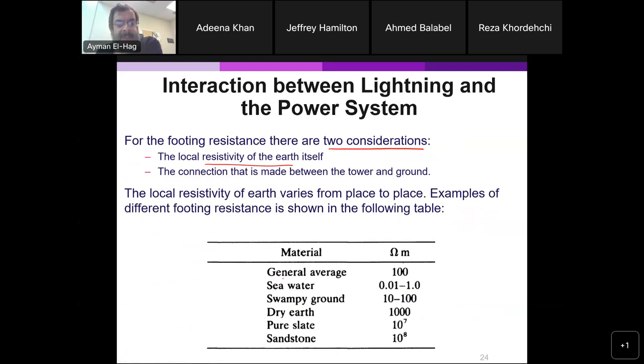So here it depends basically on the material of the soil that we have. For example, if you have dry earth, it has a very high resistivity. This is bad. Seawater, on the other hand, has a very low resistivity. Sometimes we need to apply certain treatment to the soil so that we lower the resistance. So we have to measure the soil resistance, and there are certain techniques and devices to do that.